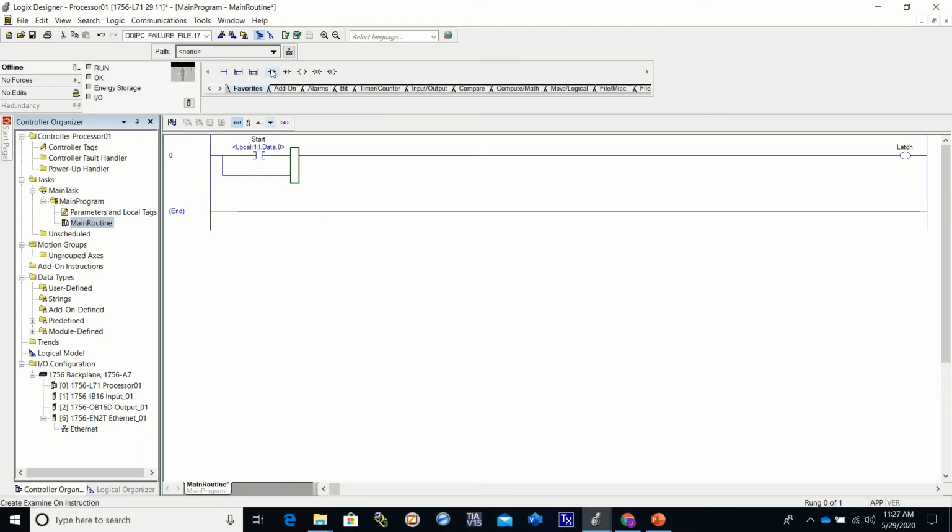The reason that we're going to put that in there is if I press this start button, I get this base bool, which is latch, which will then give me this latch input, and it will hold this on. Now, the problem with this is that if I hit the start button, this will come on, this will come on, and it will hold it on, but we can never get rid of it. So we want to add a stop button.